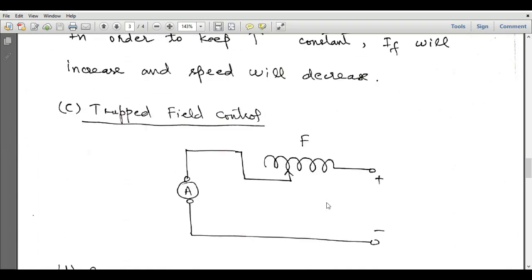Another method is the tapped field coil method. We use a variable tapping mechanism on the field winding of the DC series motor to change the number of active turns. If we move the pointer to include more turns, the flux is maximum and speed is minimum. If we move the pointer to include fewer turns, the flux is smaller and speed increases.